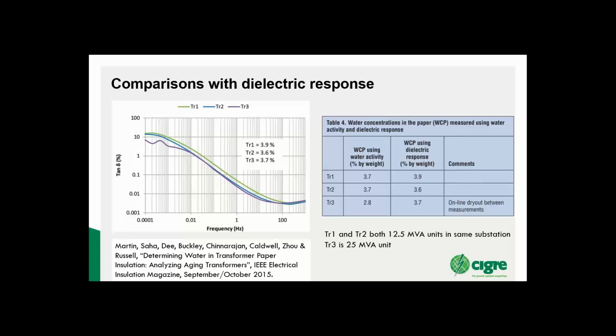Also, what can start to happen on these on-site dry-outs is that if we are drying out the oil, it takes some time for the water in the press board to come out into the oil. So in this case, we usually expect the water content from the capacitive probe to be lower, simply because we've dried the oil and now we're waiting for all that water to come back out again. But in any case, we thought it was quite a good correlation.